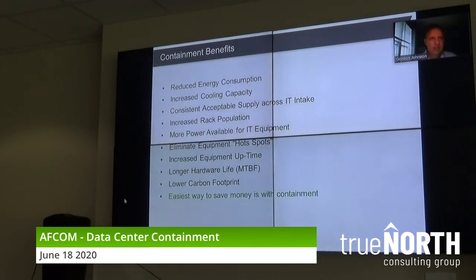And what I mean by that is, it should be able to go down your cold aisle in the data center, and if I measure at the bottom of the rack, the middle of the rack, or the top of the rack, I don't want to see a temperature change. If I see 70 degrees coming from your perf tile, I want to see 70 degrees at the bottom. I want to see 70, 71 in the middle, maybe 71 at the most, 72 at the top. Now, if I walk down to the other end of your cold aisle, I don't want to see a change. I want to see that 1 to 2 degree, maybe maximum 3, but I want to see a very small delta anywhere in your cold aisles that I walk in your data center.